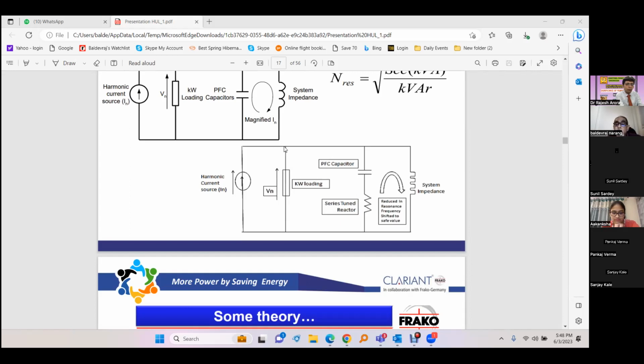And third is that some harmonics are also absorbed by this. We are normally tuning this LC circuit to the 5th frequency, maybe close to the 5th, say 189 to maybe 210 or 220 hertz. So this LC circuit is offering a very low impedance to the 5th harmonic current. So that is absorbed, and thus it is not getting exported back to the grid. In addition to the 5th harmonic, it also absorbs higher order harmonics to a lesser extent, maybe 7th, 11th, 13th, and so on.